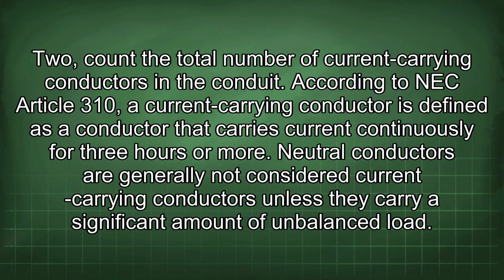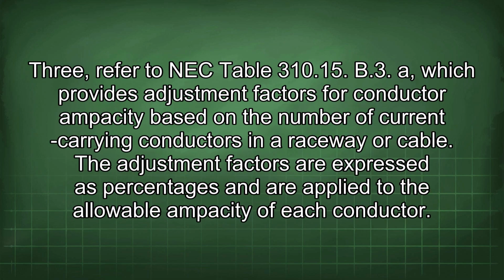2. Count the total number of current-carrying conductors in the conduit. According to NEC Article 310, a current-carrying conductor is defined as a conductor that carries current continuously for 3 hours or more. Neutral conductors are generally not considered current-carrying conductors unless they carry a significant amount of unbalanced load. 3. Refer to NEC Table 310.15(B)(3)(a), which provides adjustment factors for conductor ampacity based on the number of current-carrying conductors in a raceway or cable. The adjustment factors are expressed as percentages and are applied to the allowable ampacity of each conductor.